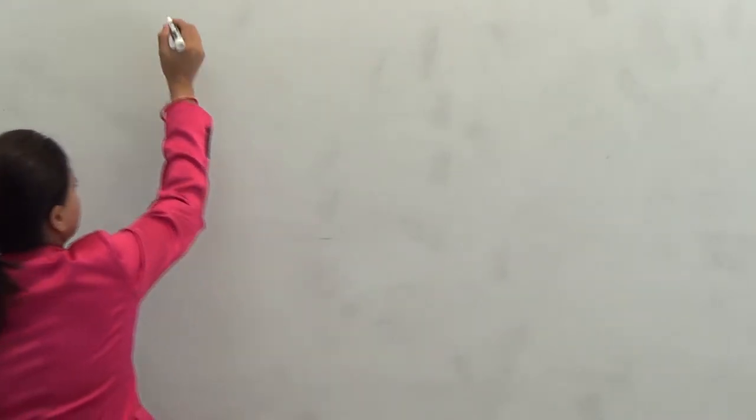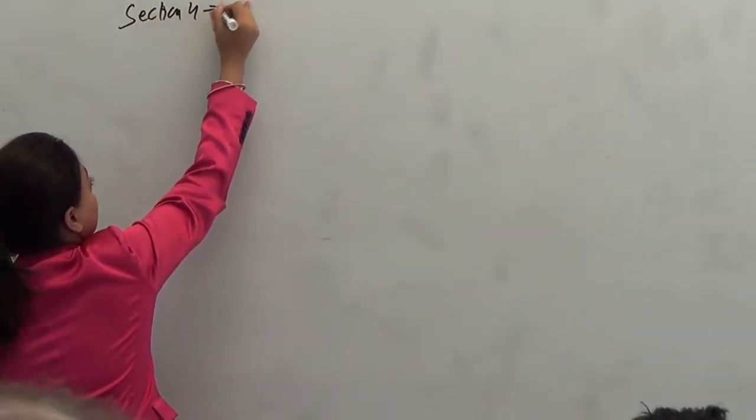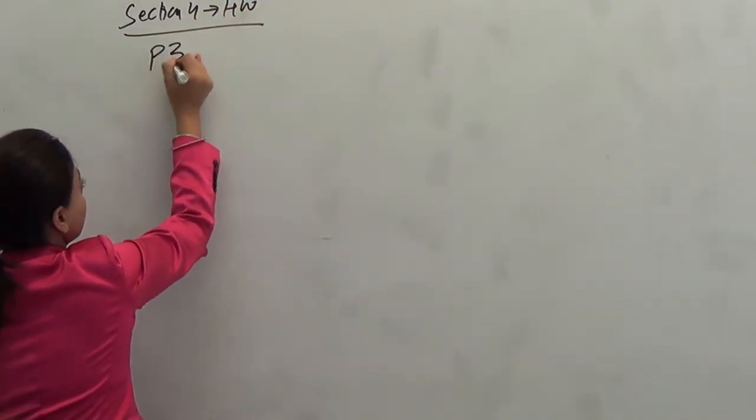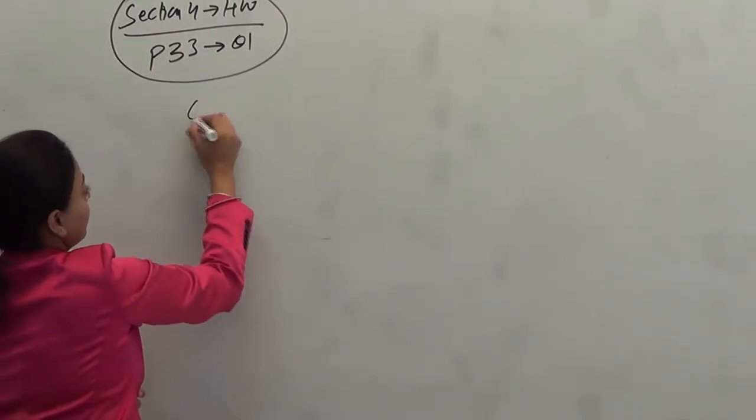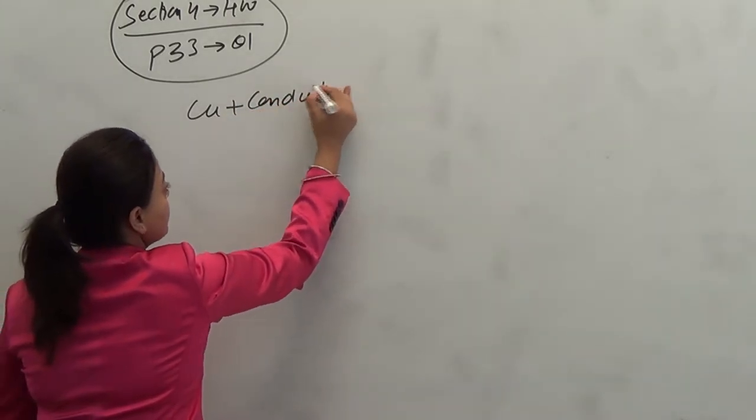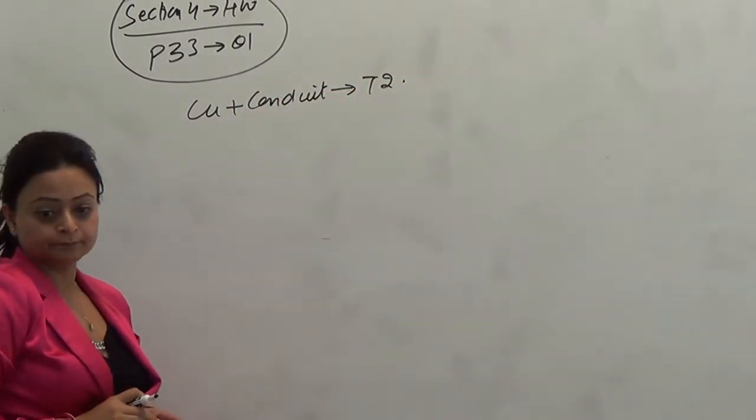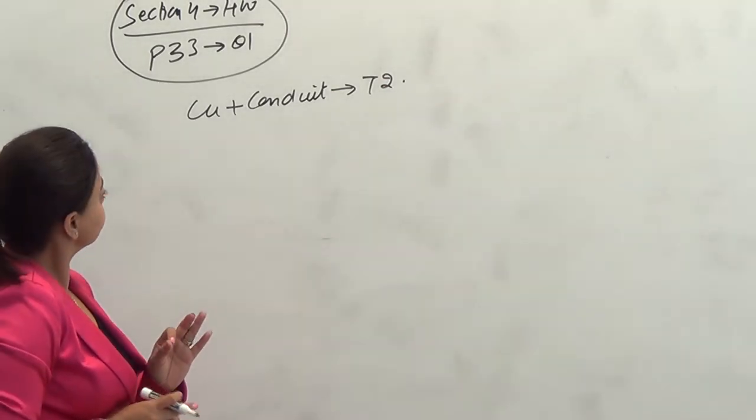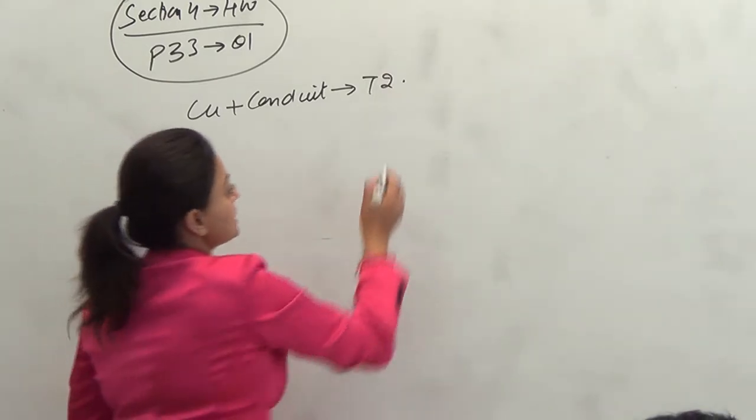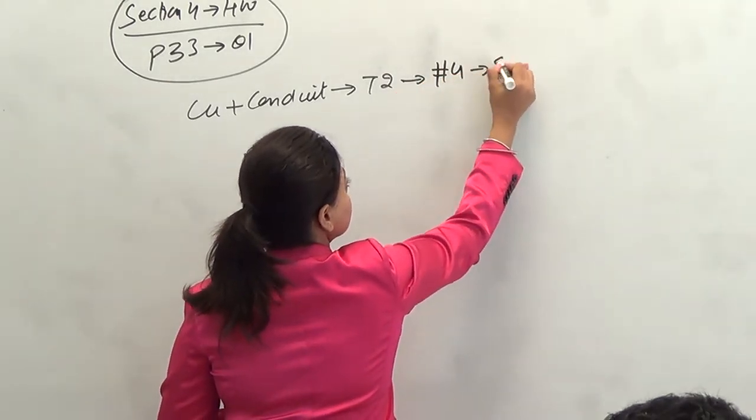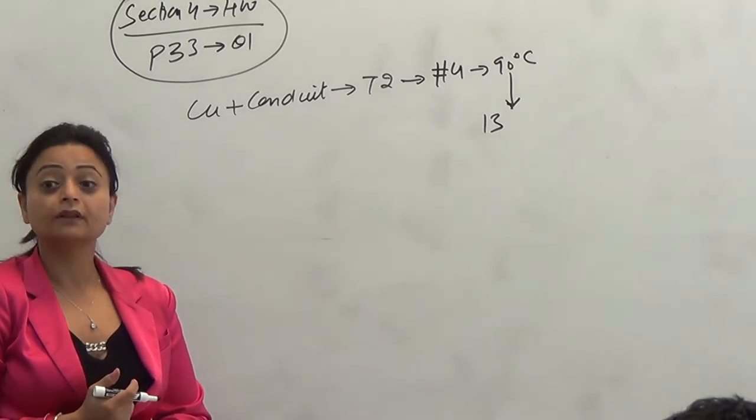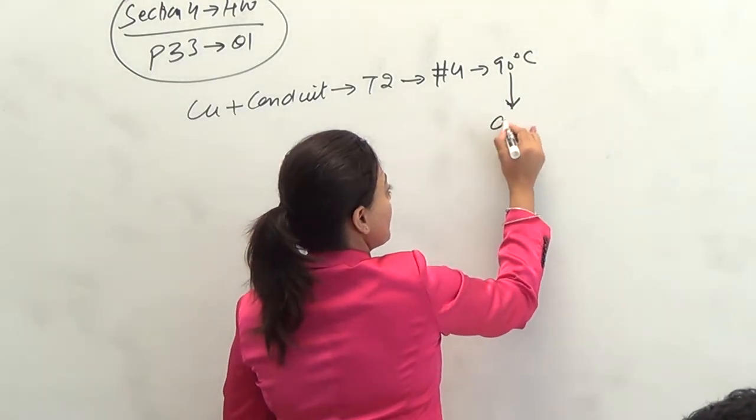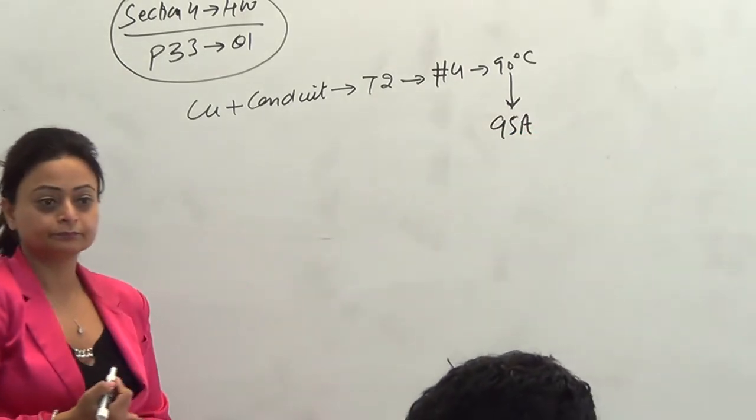How we're gonna do this? Let's do this together. If the ambient was not mentioned, we will assume 30. But because ambient is given, we gotta go one more step after finishing Table 2 and Table 5C. So, you guys are gonna do this with me. By the way guys, we are on section 4 homework, page 33, question number 1. We are given copper in a conduit, so we know we are gonna go to Table 2. And Table 2 for number 4, 90 degrees C rated. What's my answer? 95 amps. On Table 2.